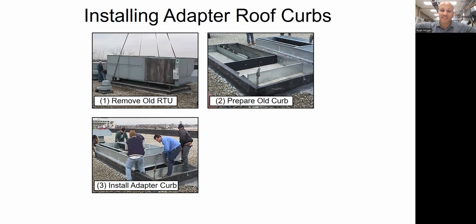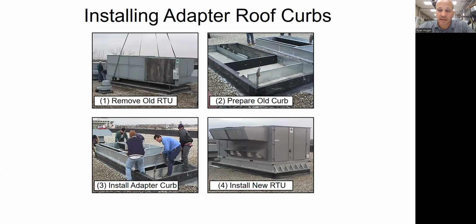And then usually you put a gasketing material down, and you'll set this curb adapter on top of it. The bottom of the curb adapter has to have duct connections that line up with the old curb. And the top of the adapter has to have duct connections that line up with the new rooftop unit. That's basically its job, to shift this duct flow over X amount of inches to the side or whatever it needs to be to make it line up. And then you set the new unit on that. So this is my old curb down here in black. The silver thing in this case is my adapter. And then this is my rooftop unit on top of it.